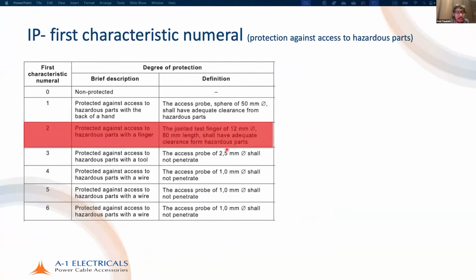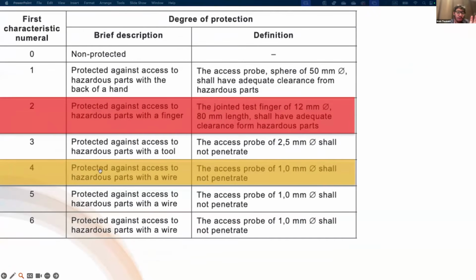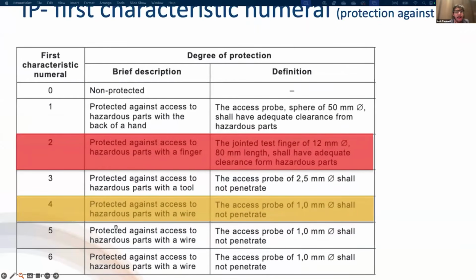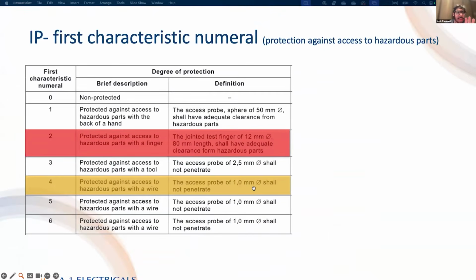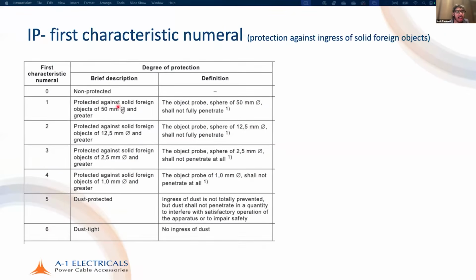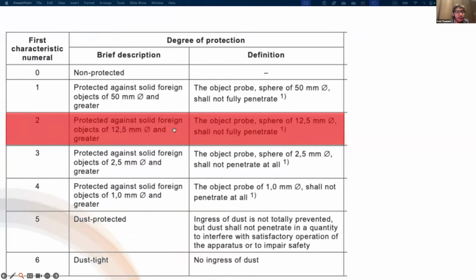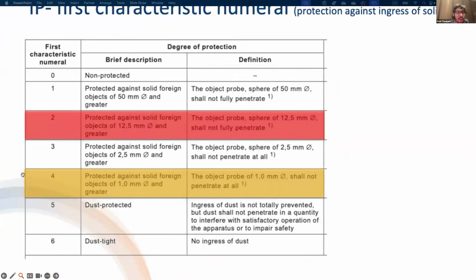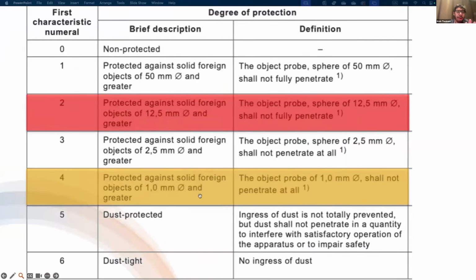If it's IP4X, or just IP4, the first characteristic numeral is 4. Protection against access to hazardous parts with a wire. Now we're talking about an access probe of 1 millimeter diameter. So if it's 2, it is this. If it is 4, it is this. It also means that there is no ingress of solid foreign objects of 12.5 diameter or greater. A probe of a sphere with a 12.5 diameter cannot penetrate. And if it is 4, then it is protected against solid foreign objects of 1 diameter. So an object probe of 1 diameter cannot penetrate at all.